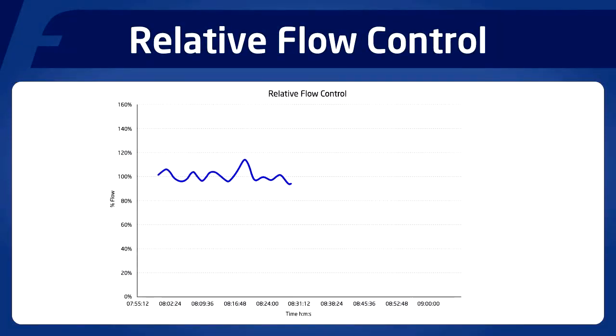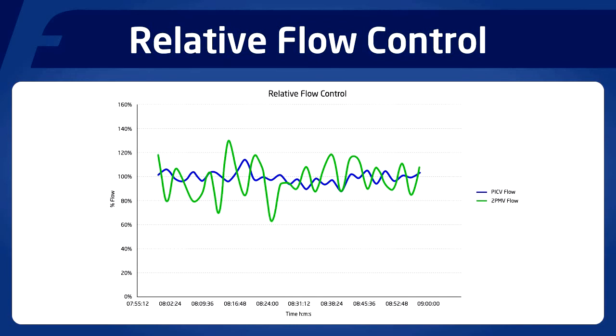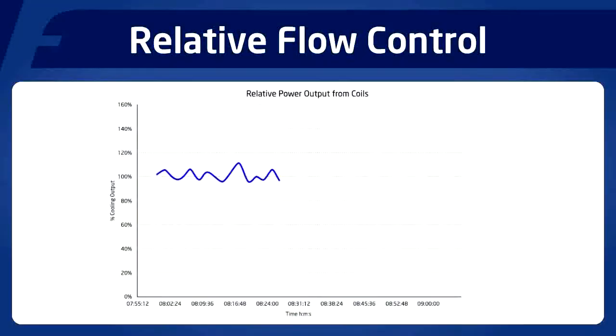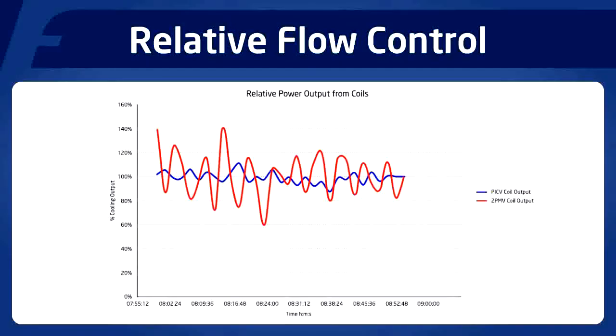We could see a similar situation occur with the relative flow control through the air handling unit when fitted with a pressure independent control valve or fitted with a two-port modulating valve. Again, the amplitude and frequency of the oscillations are higher when the air handling unit is fitted with a conventional two-port modulating valve. If we compare the relative cooling output of the air handling unit when fitted with a pressure independent control valve and two-port modulating valve, we can see once again the power output from the coil is much more stable when fitted with a pressure independent control valve.